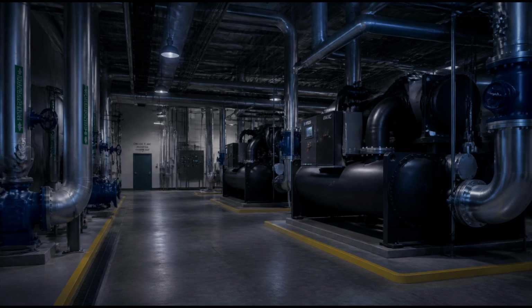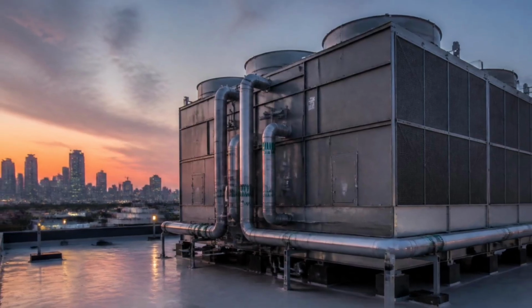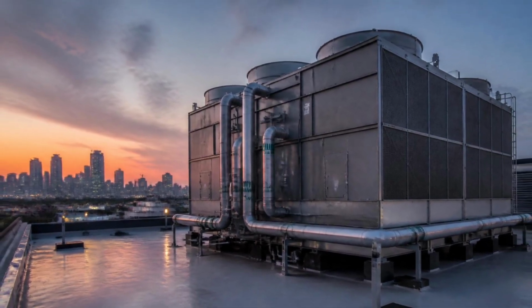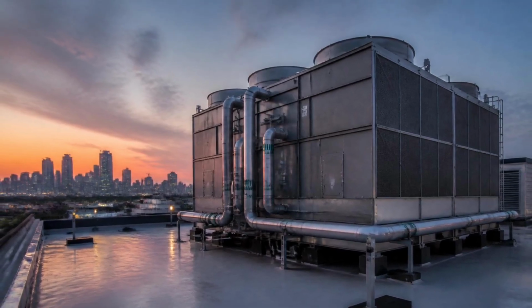Pumps move water through coils and mechanical equipment. Each loop has its own pumps, typically located near the central mechanical equipment, near the chiller, near the boiler, near the cooling tower. These pumps are sized to maintain the proper flow rate through their respective loops, pushing water at the speed needed to ensure adequate heat transfer at every coil along the way. In many systems, variable speed drives allow the pumps to adjust their output based on demand. When the building needs less cooling, the chilled water pumps may slow down, using less energy. When demand increases, they speed back up. This ability to modulate means the pumps are rarely running at full capacity, spending most of their time at a gentle, measured pace that matches exactly what the building requires.